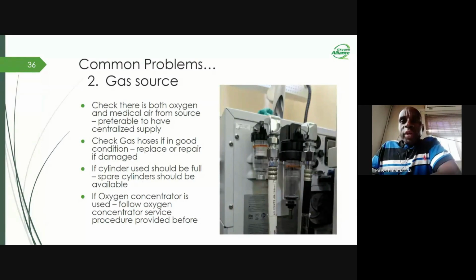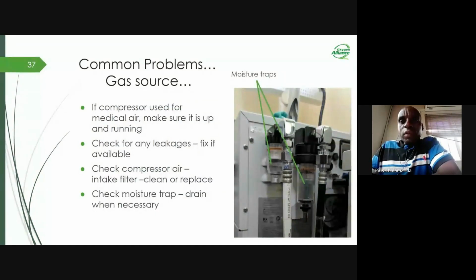So if a compressor, for example, is being used for the supply of compressed medical air, then you have to make sure that it is up and running. And also you have to check for any leakages if they are present and fix them properly. Check the compressor air intake filter. You may clean or replace it if necessary. You can also check the moisture trap and drain it.